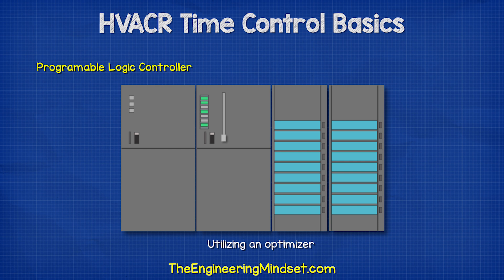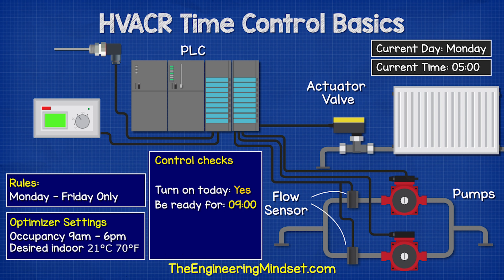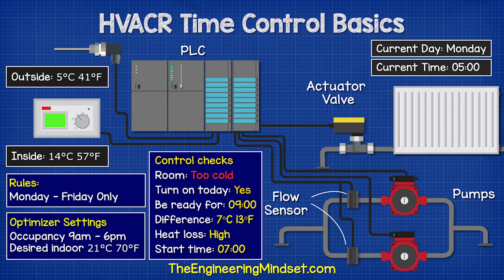A more sophisticated system, typically used in much larger buildings, will use an optimizer. For this example, we have it connected to a programmable logic controller. This will check with the clock: should the heating turn on today, and if so, at what time will the building be occupied? The clock replies yes — the scheduled occupancy time is 9am. The PLC checks the current room temperature and calculates the difference between this and the desired temperature. It then checks the outdoor temperature to calculate how long it will take to heat the building, because on a cold day it will take longer, so it will need to start earlier.